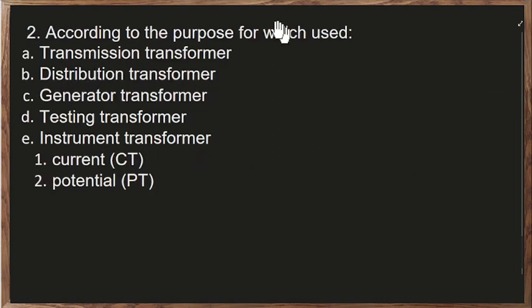Next is according to purpose, for which it is used. So transmission transformers are for transmission lines, usually located on our substations. Distribution transformers sa mga distribution line, yung karaniwan yung nakikita sa mga poste. Generator transformers are usually found on a power plant, yung kasama sa generating plant. So those are generator transformers. So we have also testing transformer, used to test other transformers or other electrical machines. Then you have instrument transformer. So it could be a current transformer, the CT, or a potential transformer, or a PT.